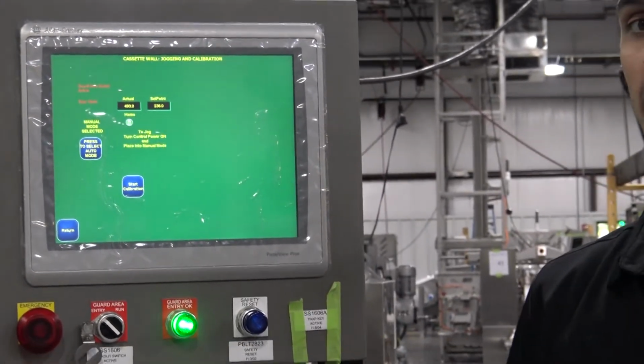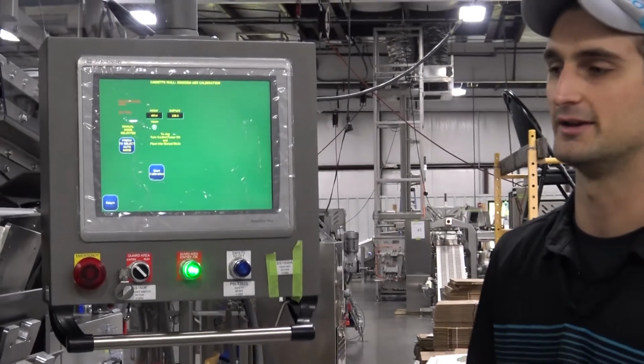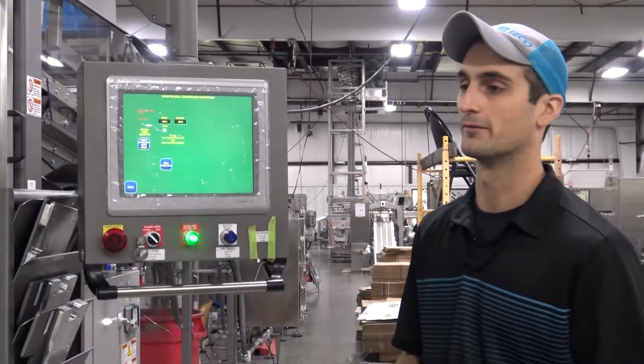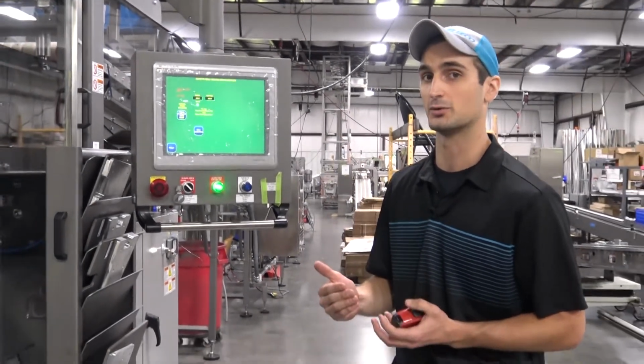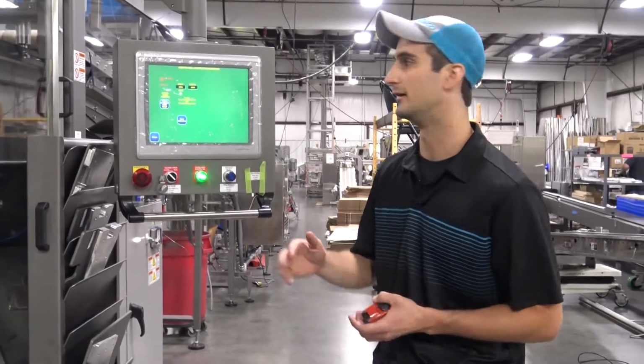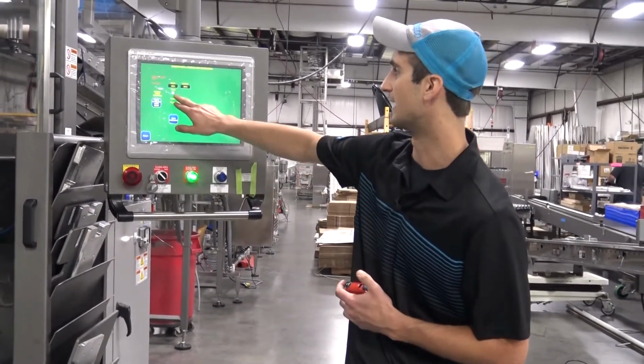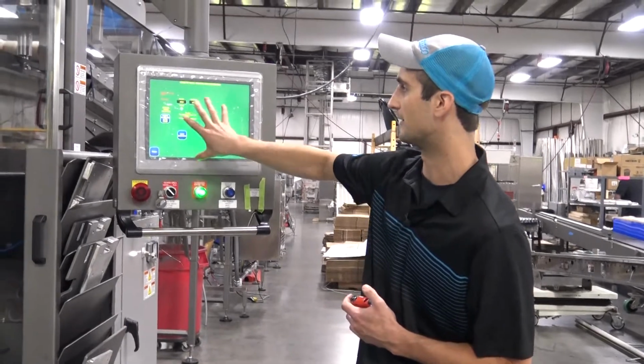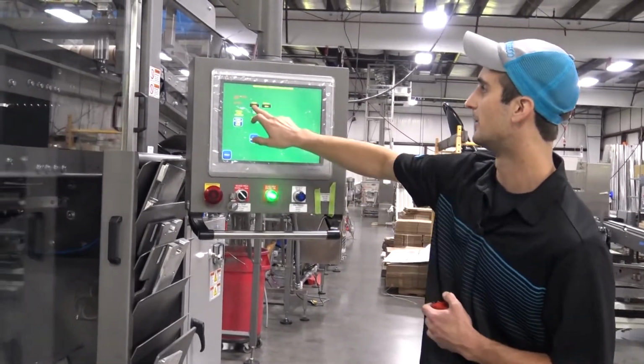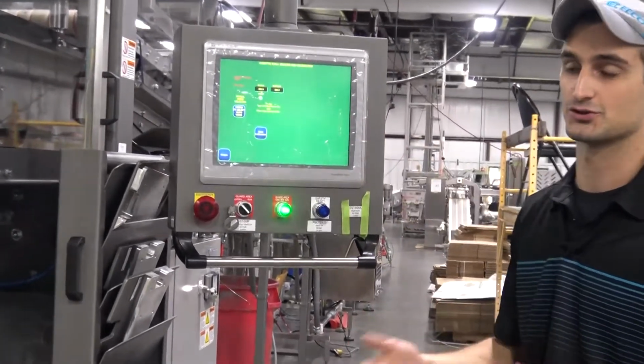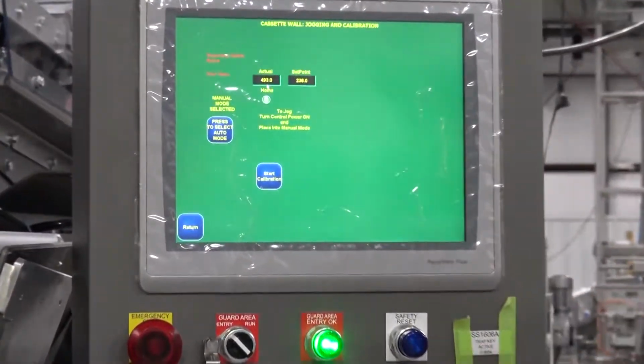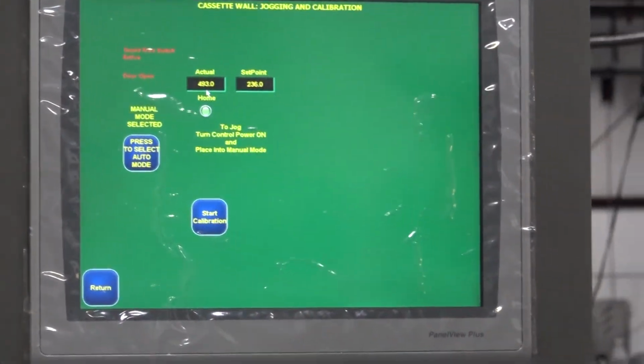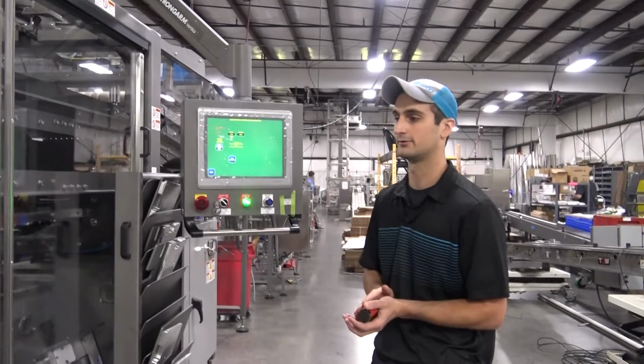And when you're going to do that, I maybe should have mentioned at the beginning of the video, is if you have a new actuator, or for some reason you see the position of that actuator is just not quite right, and you can kind of tell that with the actual position here on the screen when I measure now. It says I'm at 493, which is true because that's where we left it, and that's where I measured it too. So those are the cases where you're going to want to do that, and that's everything.